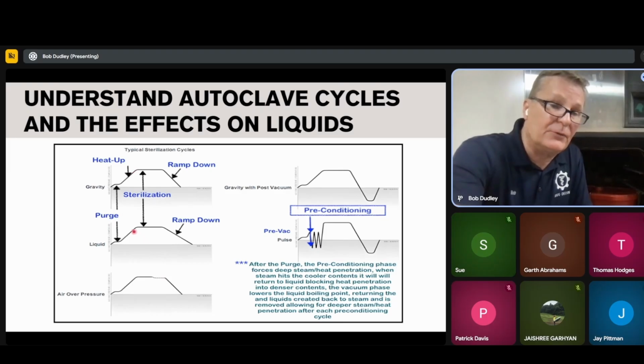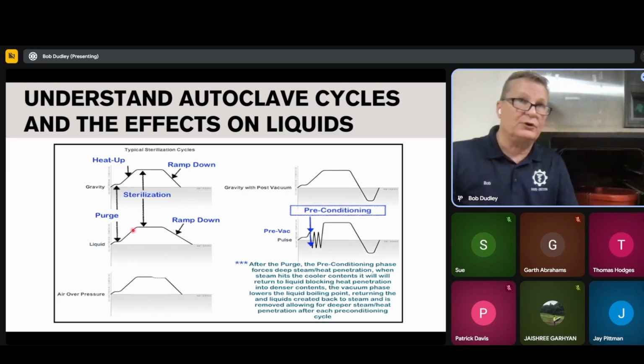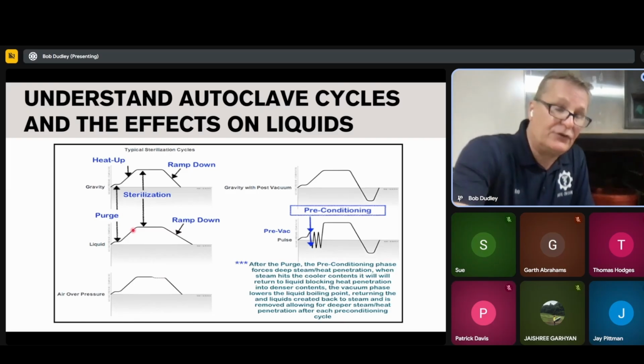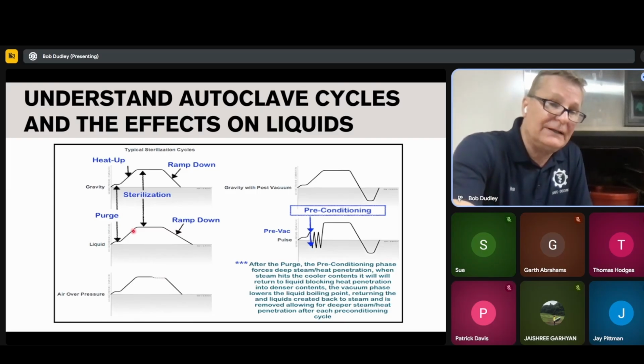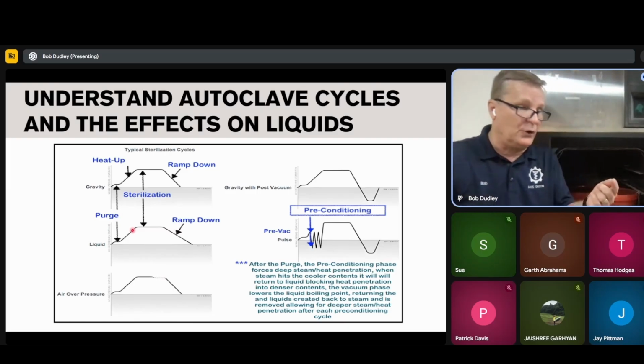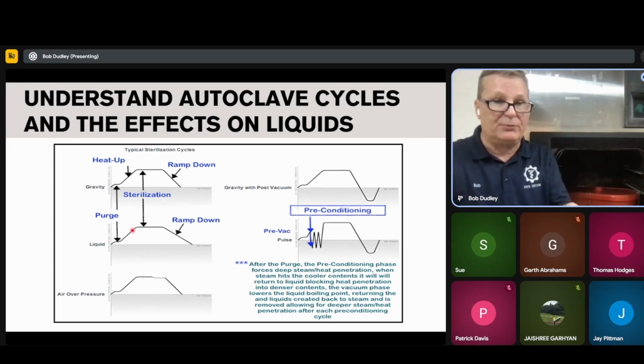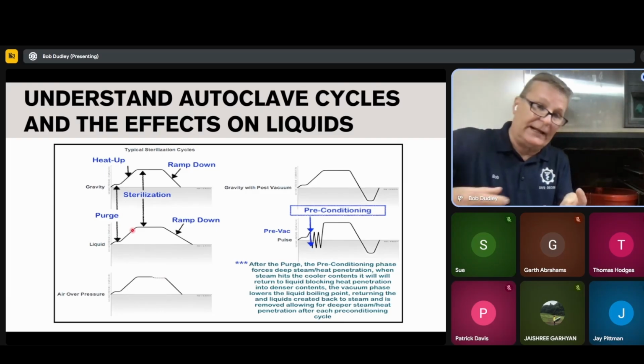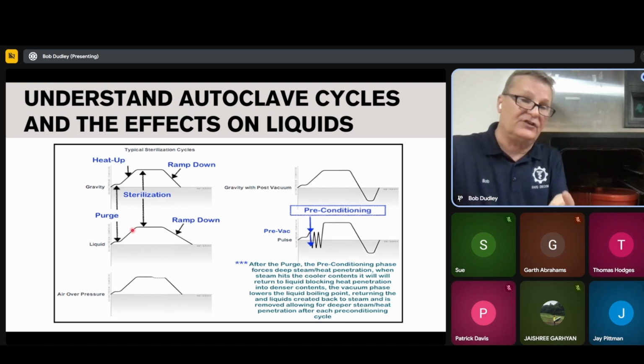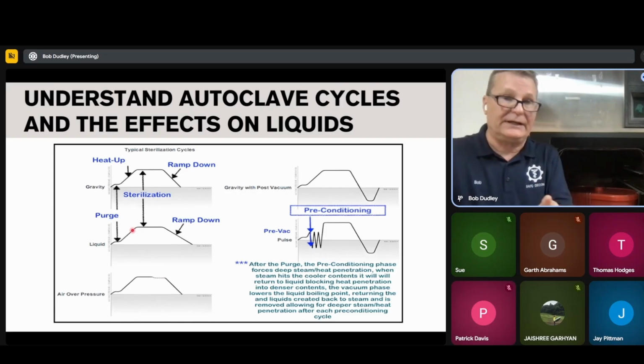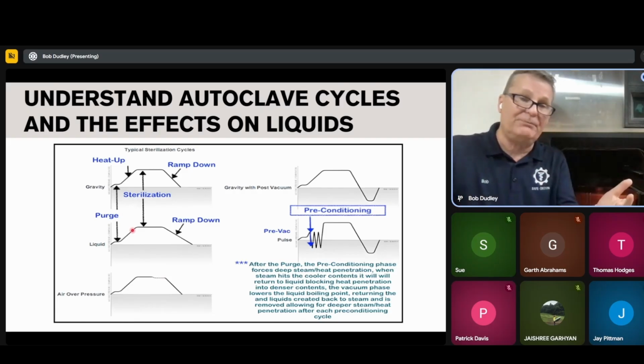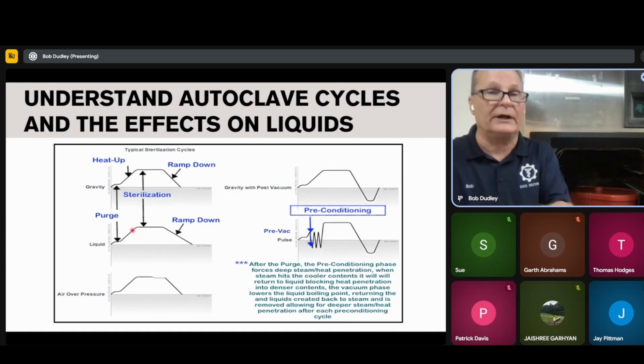And what it does is the computer makes one final check before it pushes over to sterilization. And it says, okay, let's look at everything in here. It wants to know the chamber pressure, the chamber temperature. If you're using a load probe, it's going to look at your load probe. It's going to look at the drain temperature to make sure, because the drain is the coolest spot. So it has to make sure that that temperature is up enough to kill. And then it's going to look at the pressures to make sure that the pressure equals temperature. 15 psi should equate to 121.